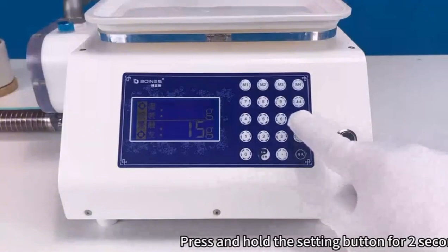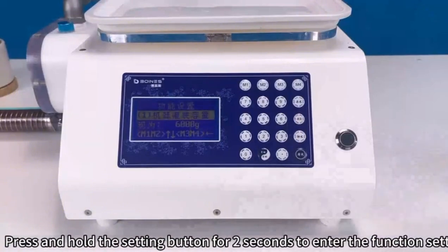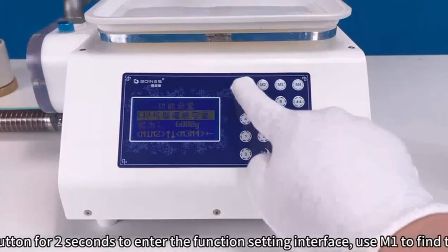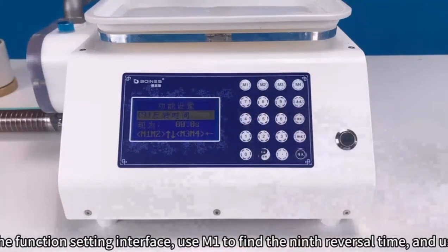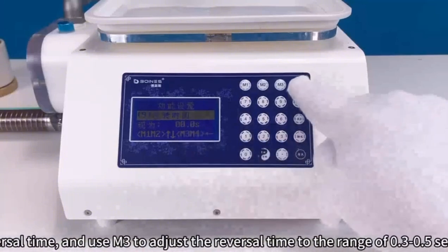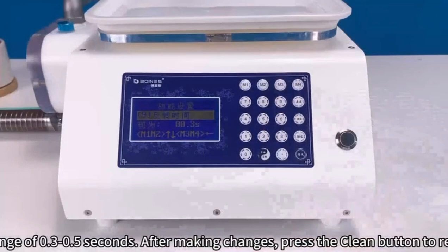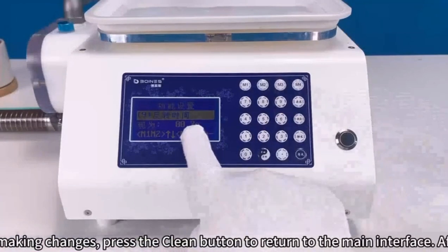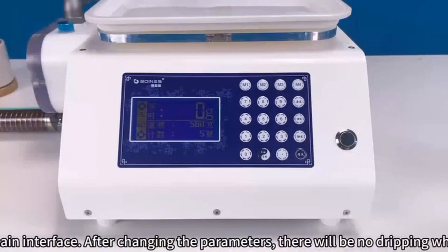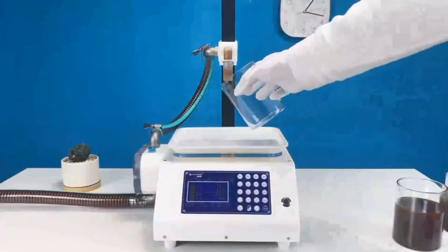Press and hold the setting button for 2 seconds to enter the function setting interface. Use M1 to find the ninth reversal time, and use M3 to adjust the reversal time to the range of 0.3 to 0.5 seconds. After making changes, press the Clean button to return to the main interface. After changing the parameters, there will be no dripping when filling again.